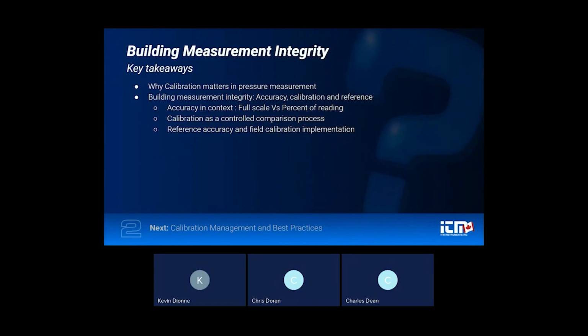Third, calibration is a controlled comparison process. It doesn't improve your instrument, it reveals how your instrument is performing relative to a reference. The integrity of that comparison depends on the stability, control, and repeatability of your calibration processes. And finally, we discussed how the different tools support different stages of pressure work.